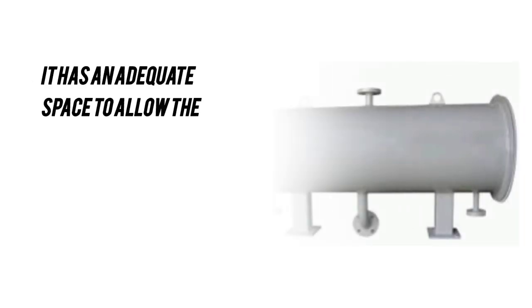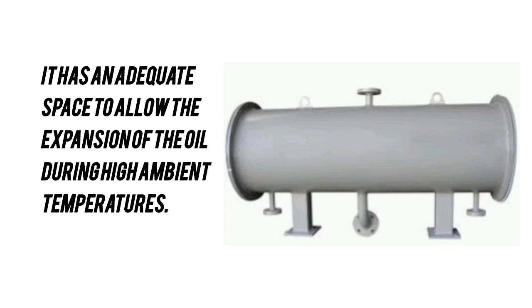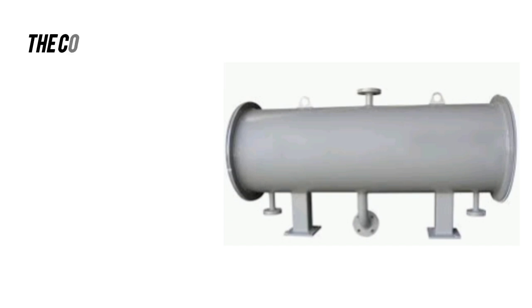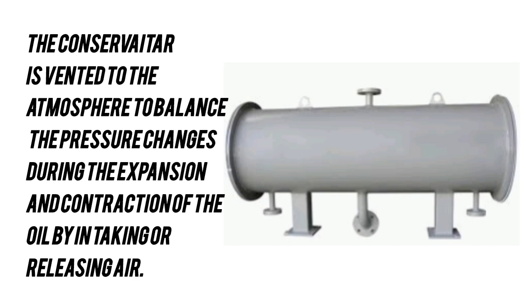It has adequate space to allow the expansion of the oil during high ambient temperatures. The conservator is vented to the atmosphere to balance the pressure changes during the expansion and contraction of the oil by intaking or releasing air.